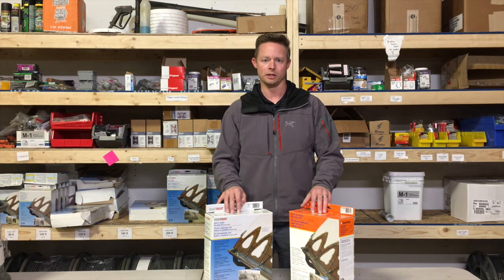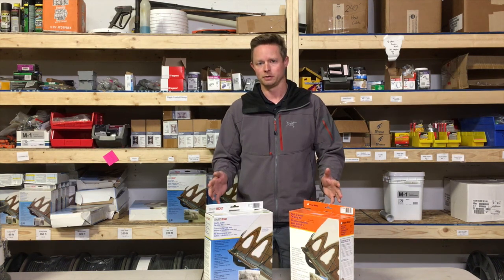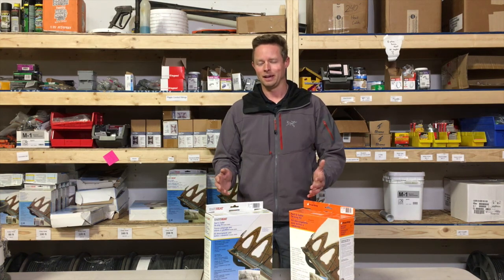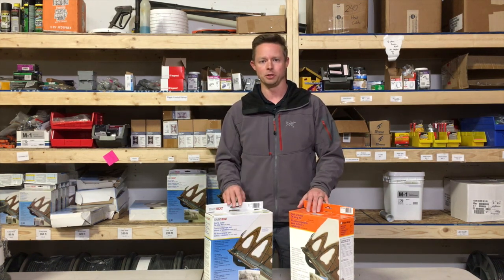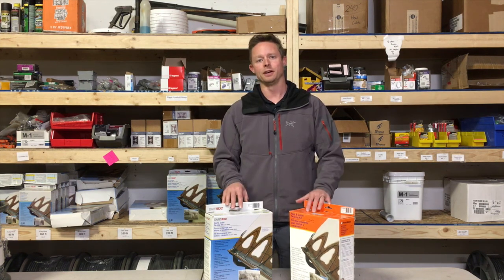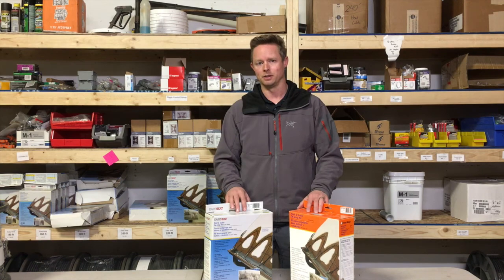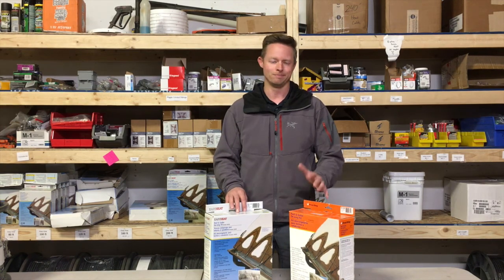Another disadvantage is the warranty — you only have a two-year warranty on this. And life expectancy: six to seven years is expected. If you get beyond that, you're pretty lucky. We've seen this fail after three or four years. These are pre-terminated kits, so they should last a while, but not always.